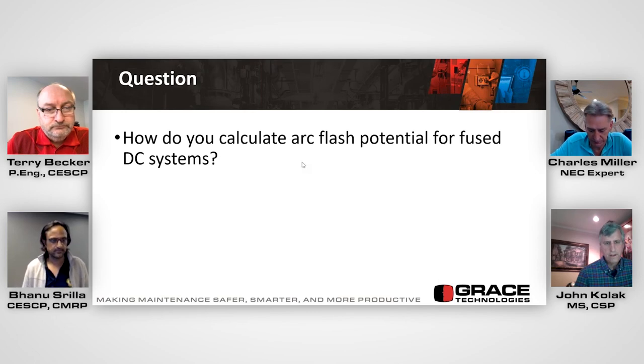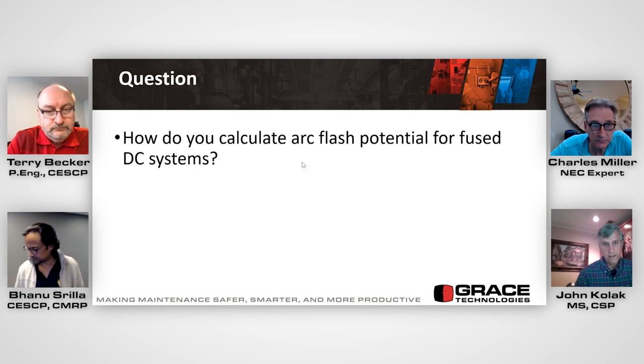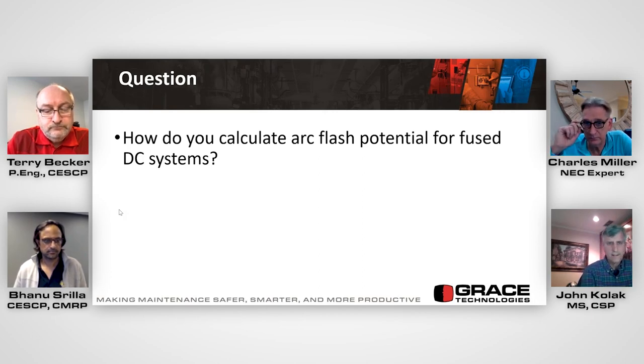Well, we've got ways of calculating this. The software that we use now has the ability to model DC systems. Like everything else, if you correctly model the system - and this is usually an issue with solar arrays - we use a different set of calculations, but it's just like an AC system. We're able to model it and use software to calculate it out. All of this also exists in Annex D of the 70, which gives you all the various formulas. Some of the formulas in there, if you're interested and you've got a pocket protector, you can actually go ahead and figure out what's going on in DC systems as well. It's a known quantity, we can use the software to do it.